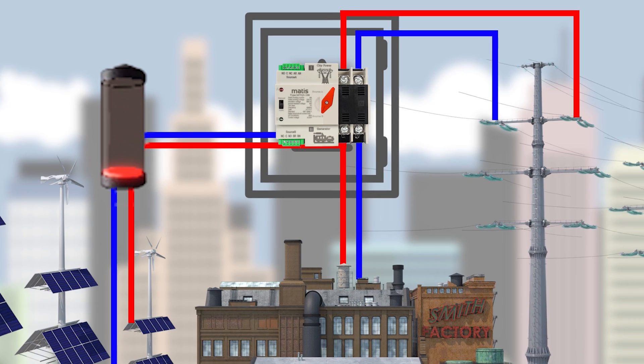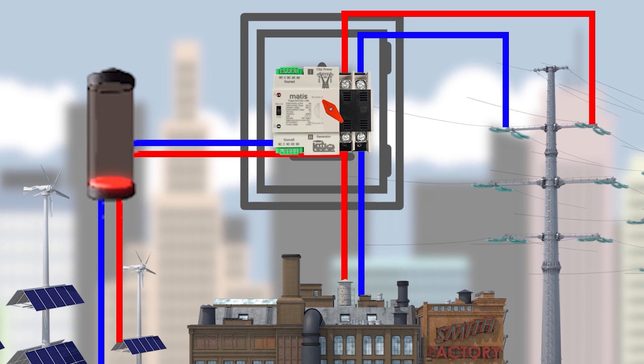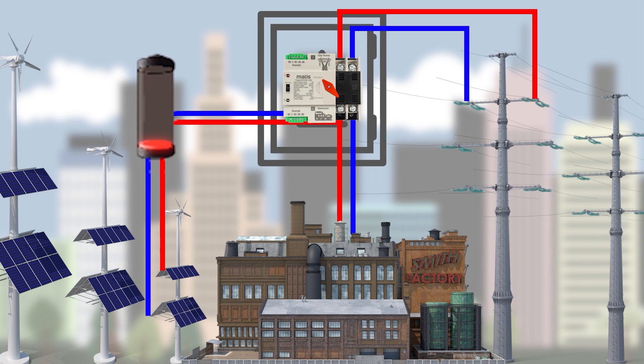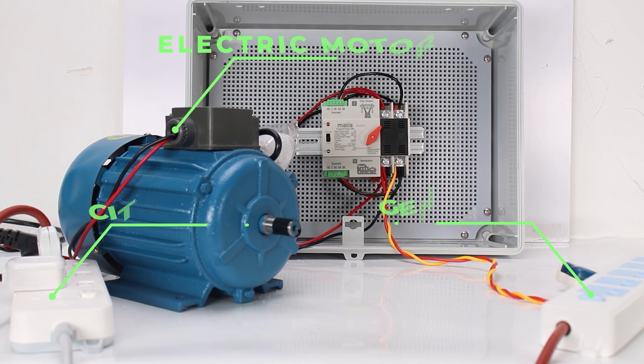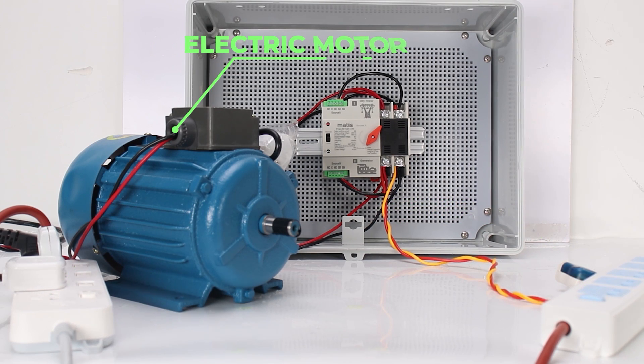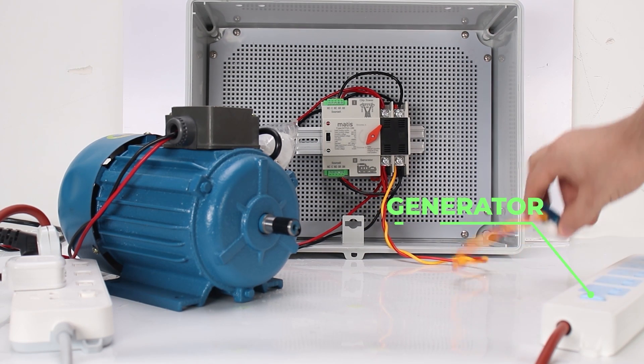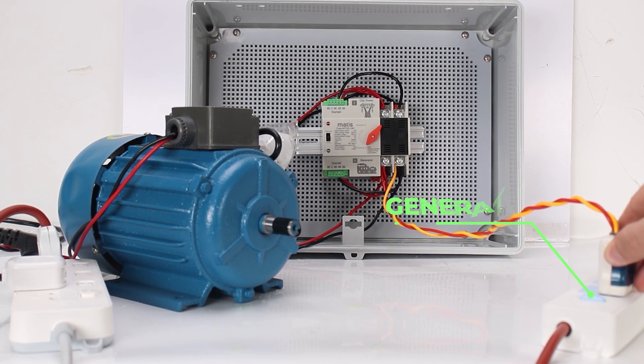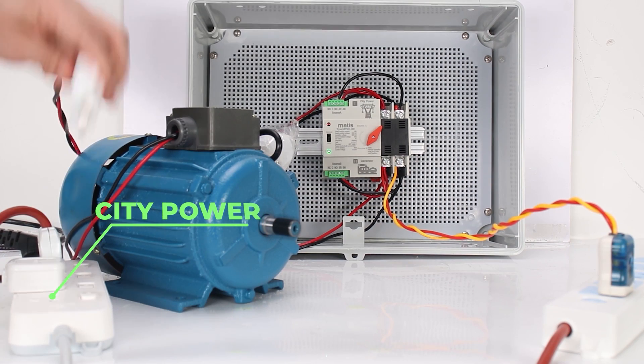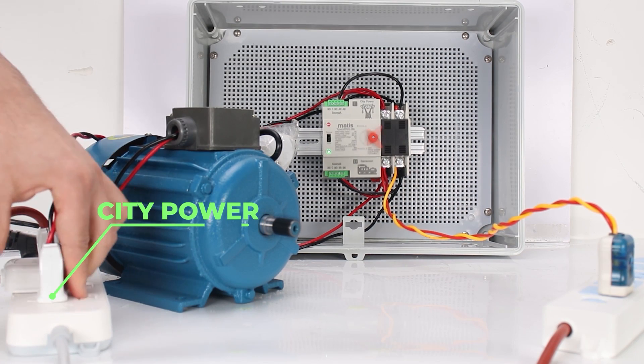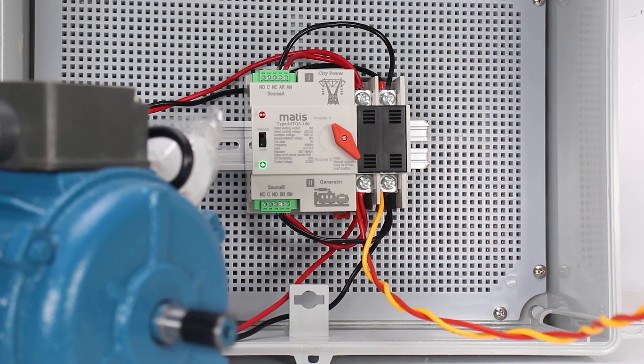At the time of battery discharge, the MTQ3 device will automatically switch to the city power supply system and continue to supply electricity to your object. For a good example, we simulated two power sources for MTQ3 and connected our electrical motor to it. Now we supply electricity from an alternative power source, but after the energy on our battery and generator is used up, the switch automatically switches the lever from state B to state A, and the power supply already comes from the city power supply network.